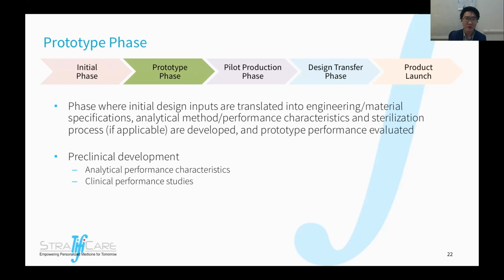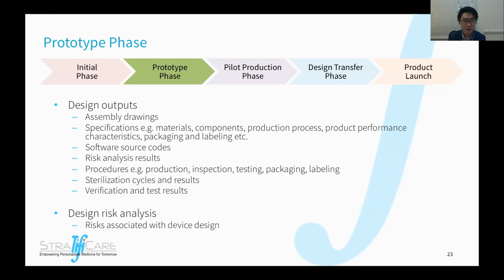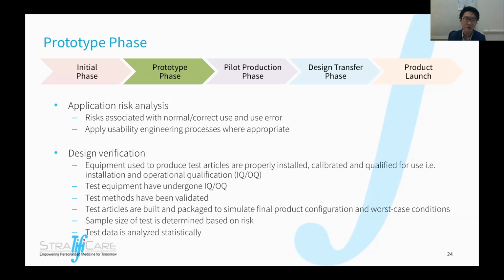And so next will be the pilot production phase. This part is pretty difficult to actually do in-house in the academic setting because of the instruments that are required. And as mentioned earlier, it's very hard to do IQOQ or proper PM and calibration for common shared equipment. This is also the phase where we start to generate design outputs, and we have to identify the risks involved in the design and try to come up with methods or change the designs so as to reduce the risk as much as possible, and also evaluate what kind of risk can possibly arise when the user is using the medical device.